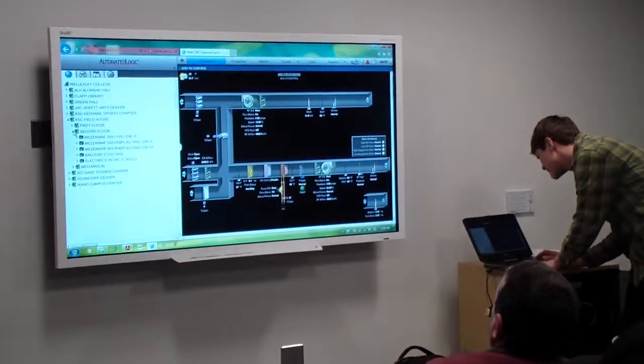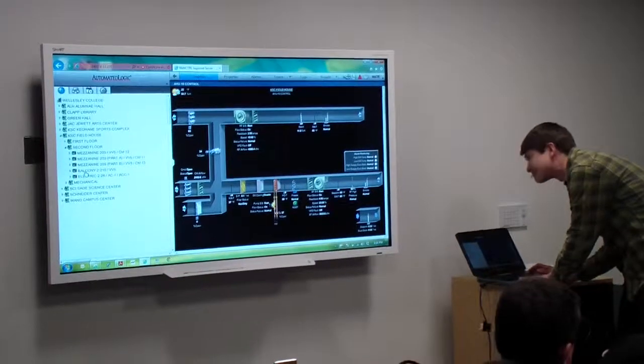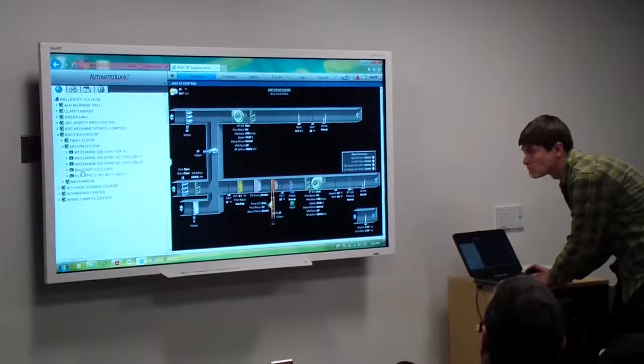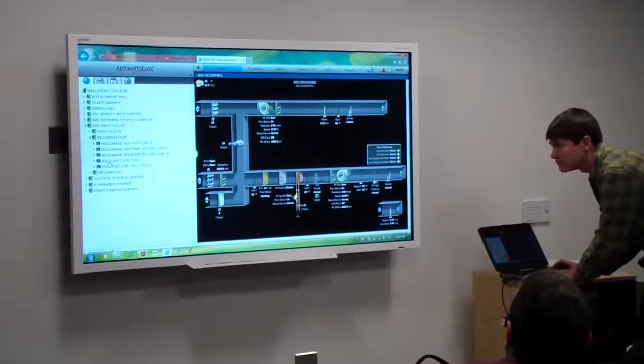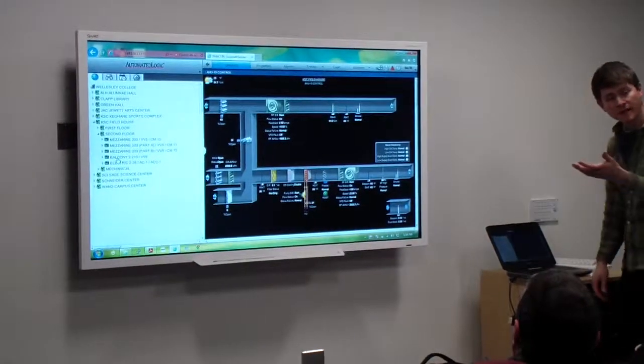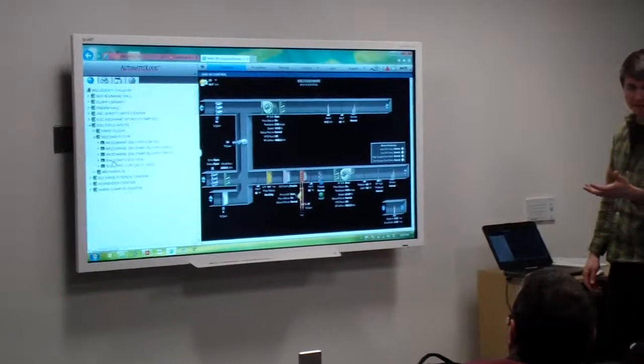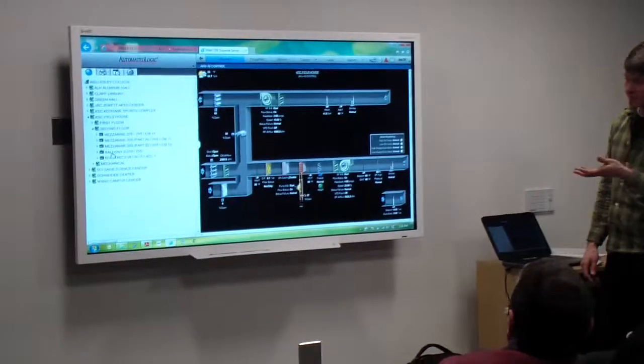So, finish up with the second floor. It also has a CO2 sensor on it, so that would take an adjustment. As the CO2 increases, it'll determine at that point that it does need some more outside air, and it will start to react appropriately.